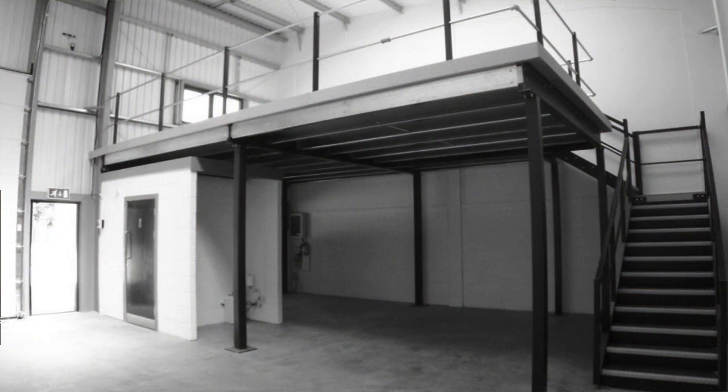Mezzanines are allowed to bypass certain fire safety considerations because, unlike ordinary stories, they are in another room, where occupants of the mezzanine are more aware of any fires that might originate in that room. The mezzanine has what used to be called a common atmosphere with the room in which it is located, so greater awareness of smoke and fire is possible. Being in the room is therefore integral to the very essence of a mezzanine.